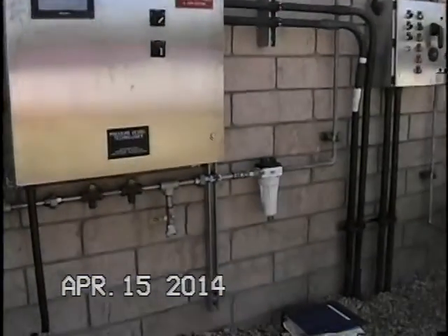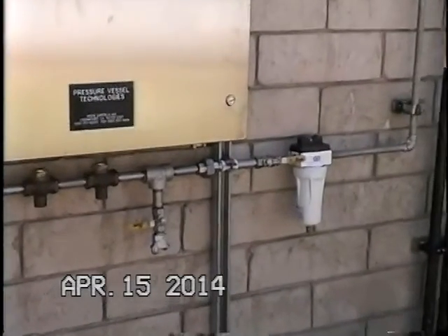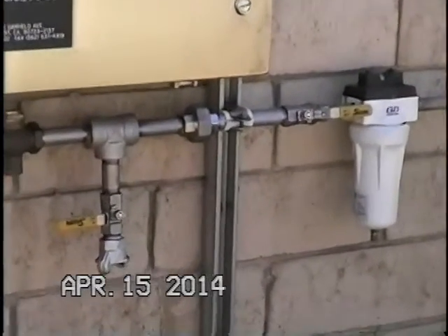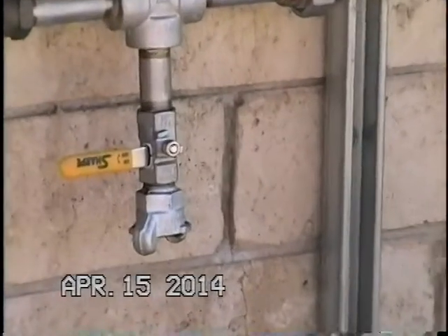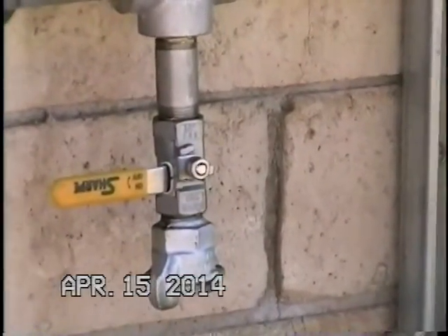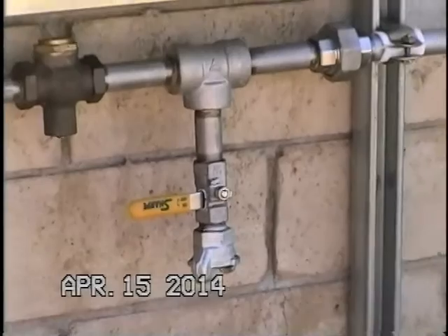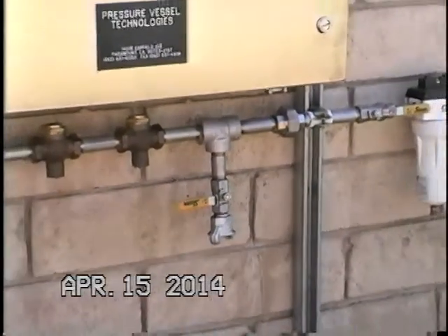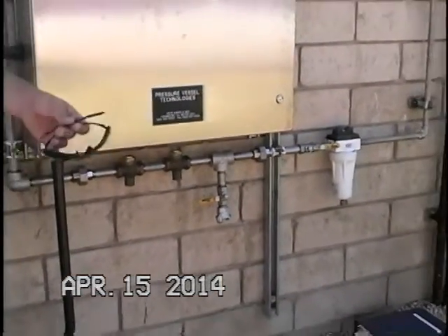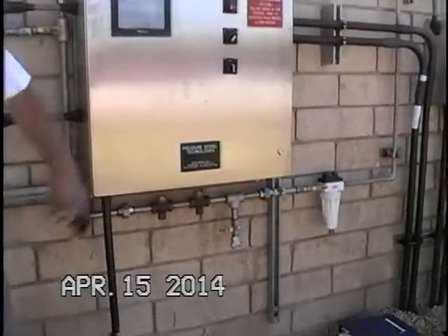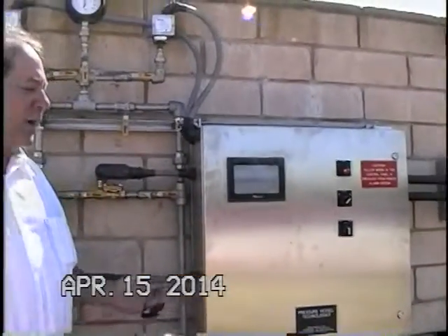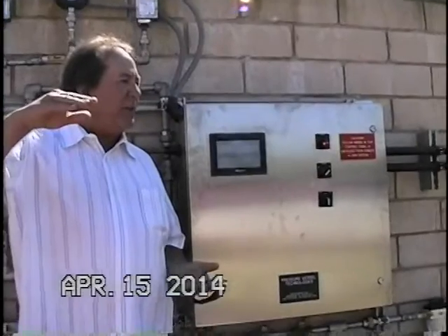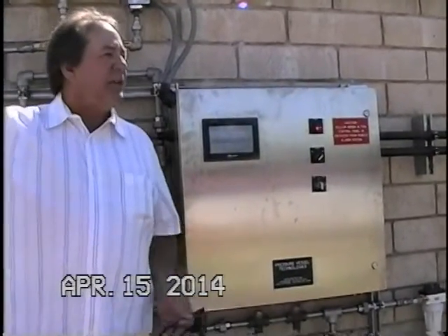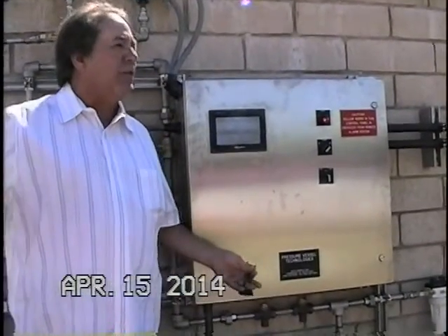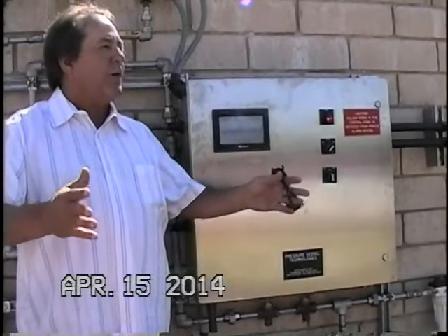What you have here is an auxiliary fill. In case you ever had the compressor fail and you needed to add air, you can bring in a portable air compressor at that stage, and then you could actually put it online. It's mainly there for if you did maintenance and you drained the tank out, you'll need to fill the tank back up to steady state and then charge the tank. It's much better to charge the tank with a larger portable compressor.